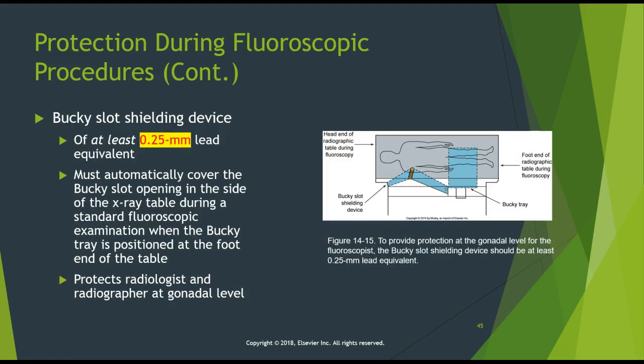The Bucky slot shielding device. Now this is different than the curtain, you guys. If you notice on your fluoro tables, you usually move the Bucky tray down to the foot of the table when you're using the X-ray tube or anything else on that table, when you're taking overheads, things like that. When you move that Bucky down to the foot of the table, there should be a device called a Bucky slot shielding device that automatically covers that slot opening, okay? It's imperative that this is in working condition because it protects the radiologist and anyone else in the room, the radiographers, at the gonadal level.